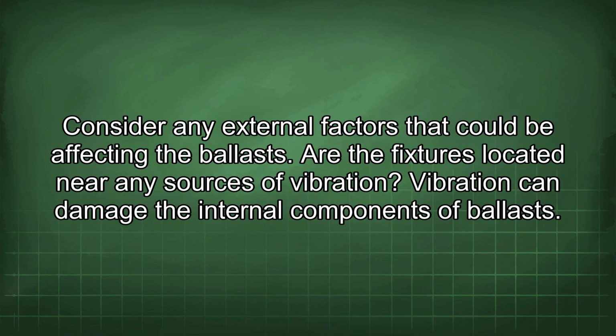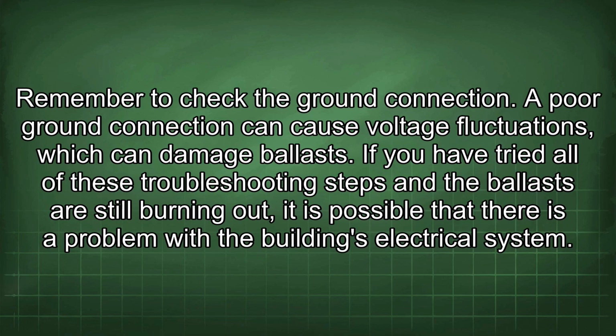Consider any external factors that could be affecting the ballast. Are the fixtures located near any sources of vibration? Vibration can damage the internal components of ballasts. Remember to check the ground connection. A poor ground connection can cause voltage fluctuations, which can damage ballasts.